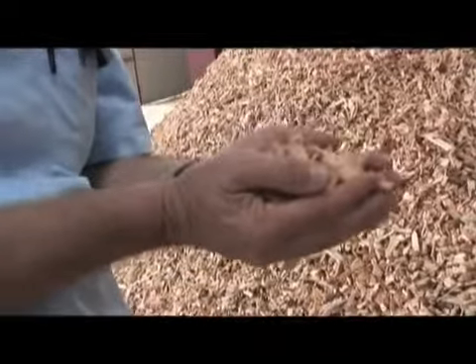Chips have the advantage of the least energy input to produce your fuel, and therefore should be at a slightly cheaper price per kilowatt hour of heat. The disadvantage is that if you're transporting over a long distance it's bulky, so you need a larger volume per kilowatt hour. Chips are ideal for local delivery — we take the wood from within 10-15 miles away and all our customers are within that range.